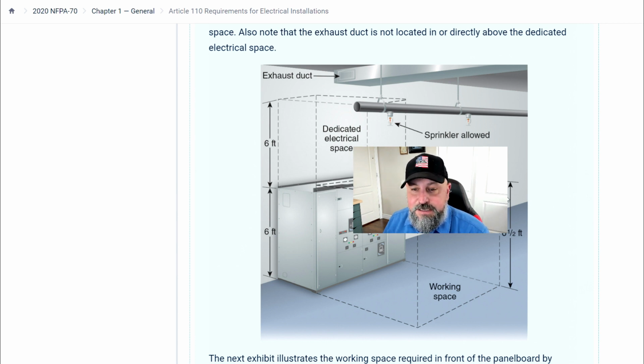It's also 6.5 feet, this dedicated space, right? So that whole 3 feet, 4 feet that we were talking about, 3.5 feet, that extends to the height of the equipment or 6.5 feet, whichever is lower. So if the equipment extends higher, then it's that height. If the equipment is shorter than 6.5 feet, then it extends to 6.5 feet. So not only do you have to have this workspace in front here, but that extends all the way up to the height of the equipment. Now, you don't get this dedicated electrical space over here in your working space, but it is up to 6.5 feet. That has to be clear. Nothing can be in there.